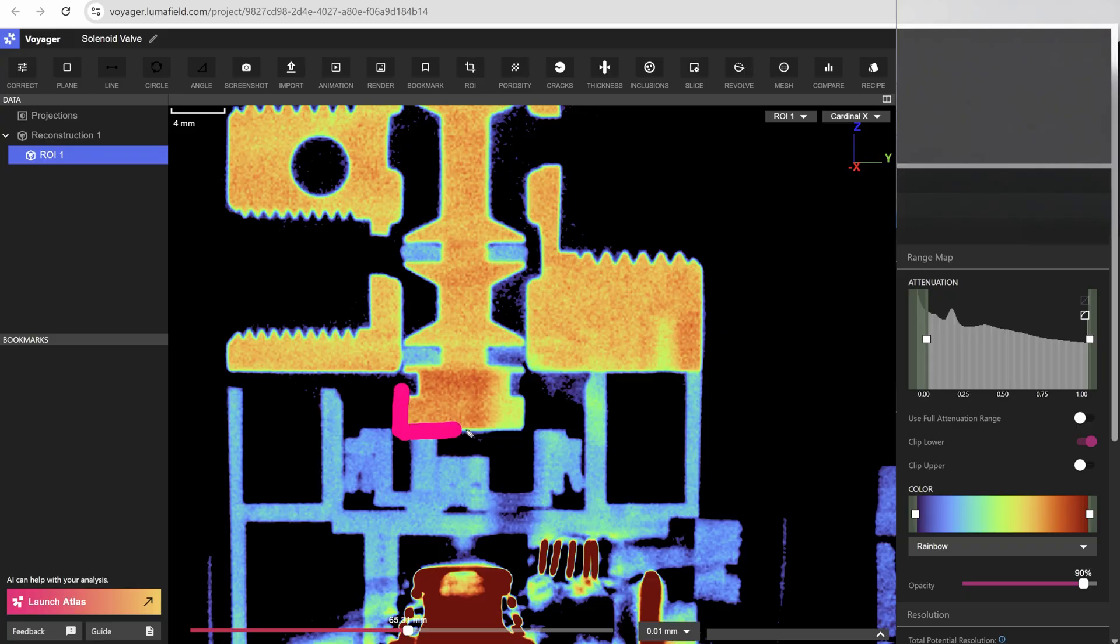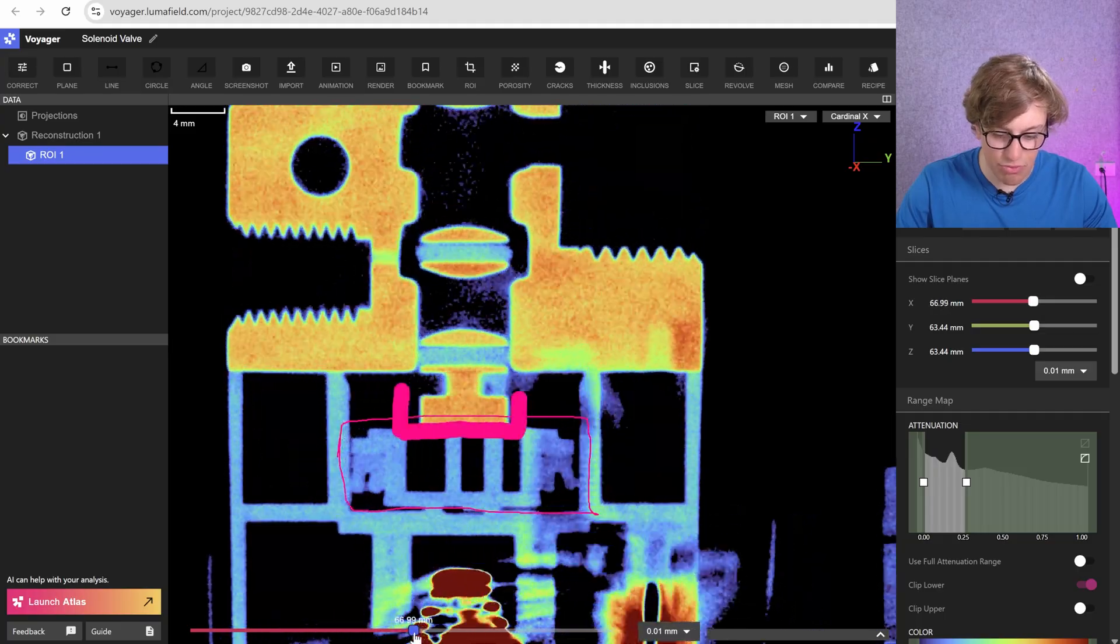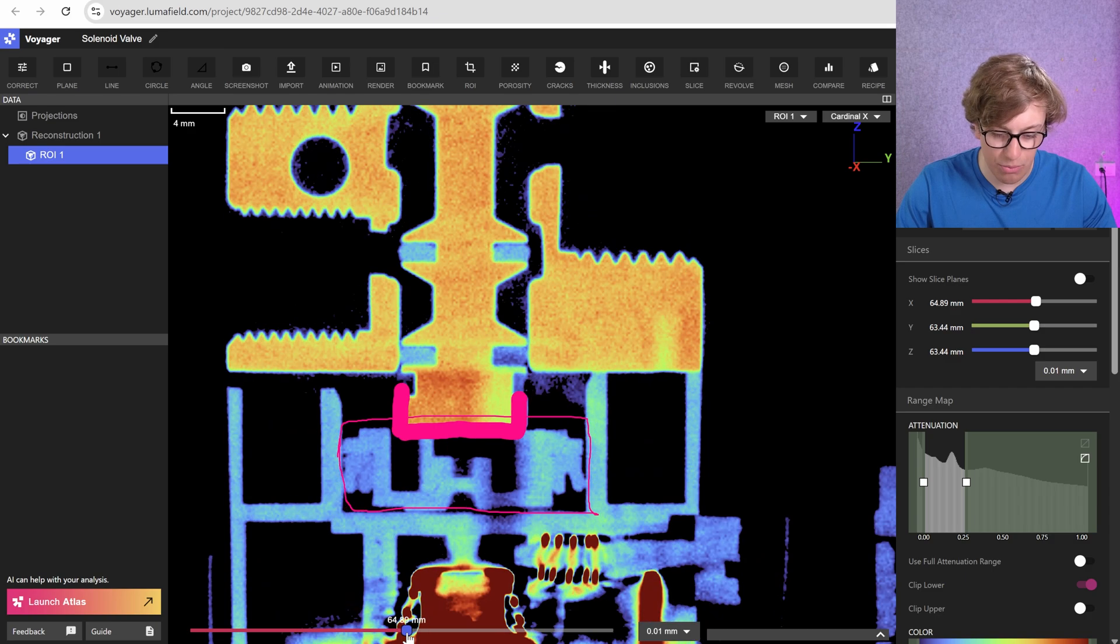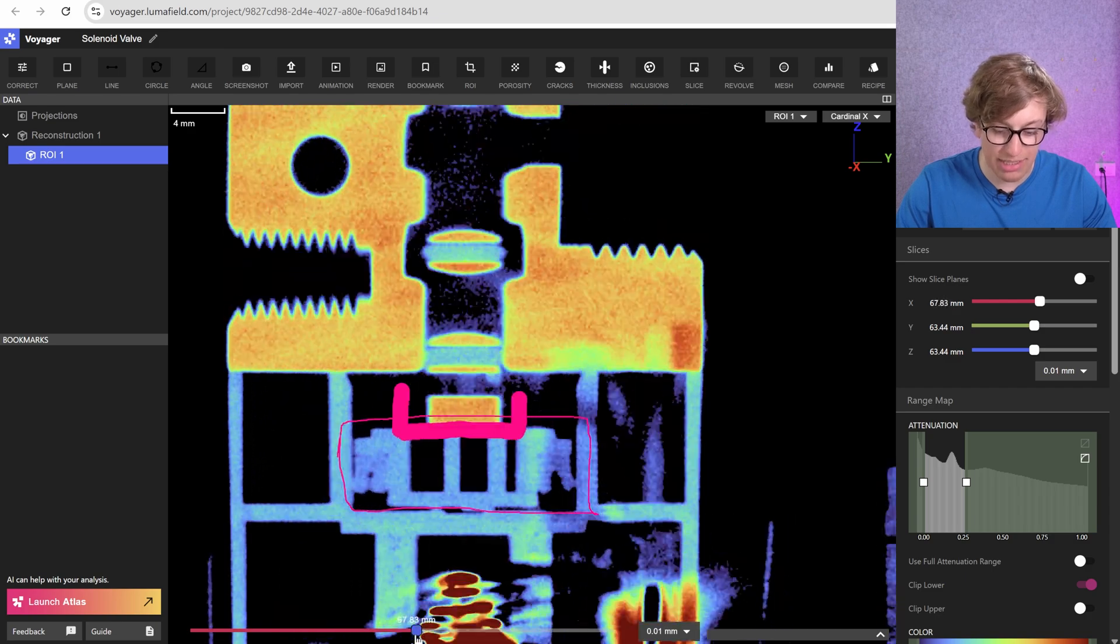We can be pretty sure it's a moving part because there's no way in hell you'd be able to injection mold this geometry into this, and it's got some fins and ribs that would be pressing against the head of the cylinder there. We know that in some way, shape, or form, the motion of this cylinder that's controlled by the solenoid is going to actually be affecting whether we have pressure on the top of this piston or not.